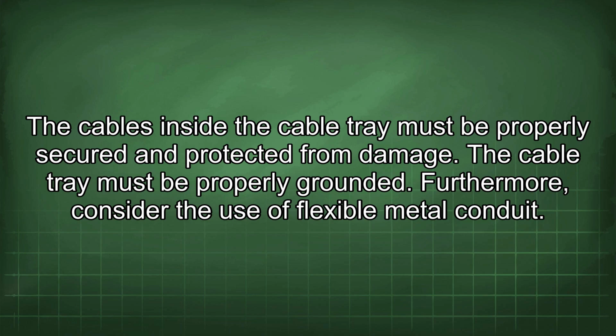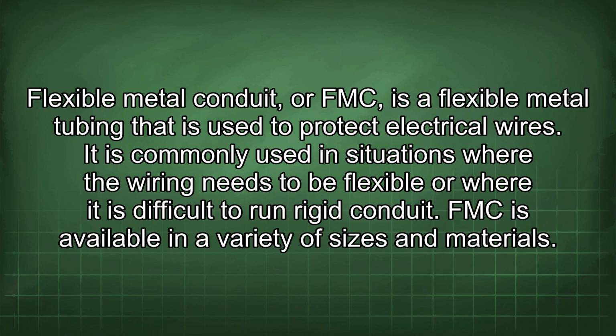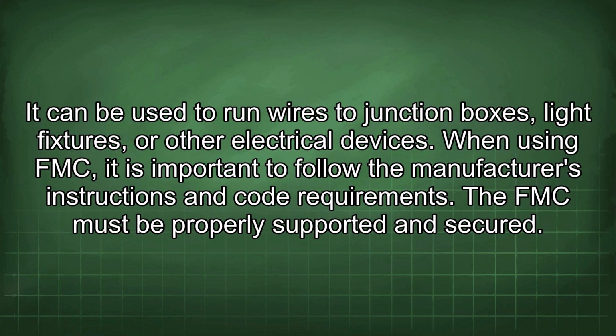Furthermore, consider the use of flexible metal conduit. Flexible metal conduit, or FMC, is a flexible metal tubing that is used to protect electrical wires. It is commonly used in situations where the wiring needs to be flexible or where it is difficult to run rigid conduit. FMC is available in a variety of sizes and materials. It can be used to run wires to junction boxes, light fixtures, or other electrical devices.